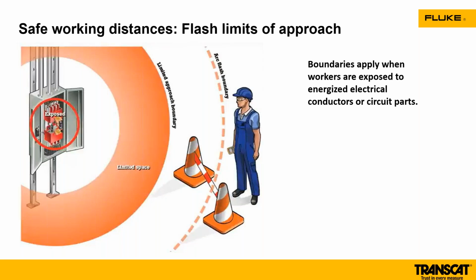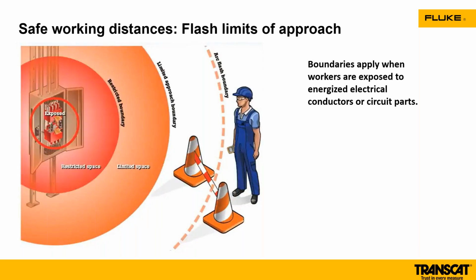They're getting closer and closer to that arc flash environment. And finally, the critical one is going to be that exposed restricted space. This is where all the work is really happening. You want to make sure that you have the correct PPE, the correct equipment, and the correct meters to be working in this environment, because that's where the potential and worst of the arc blasts could happen, in that restricted space. All of this information is part of the NFPA 70E.